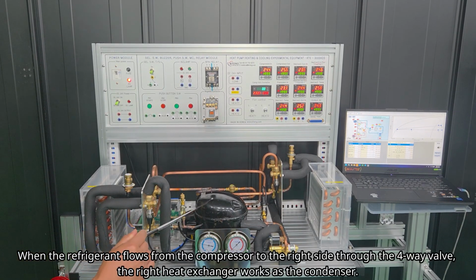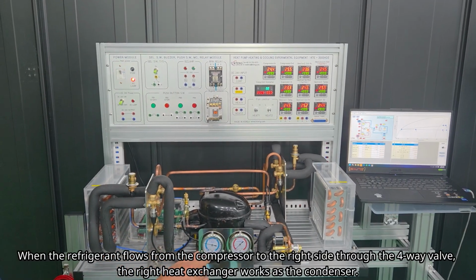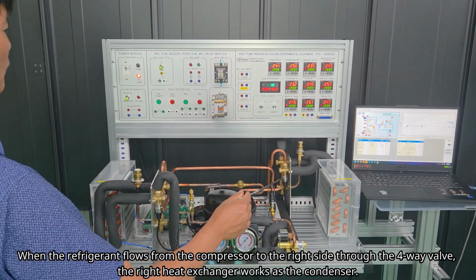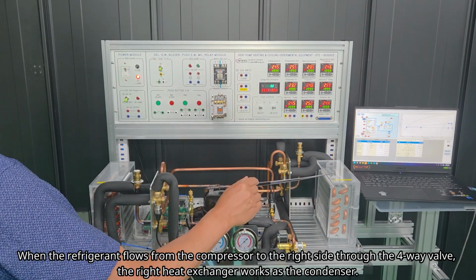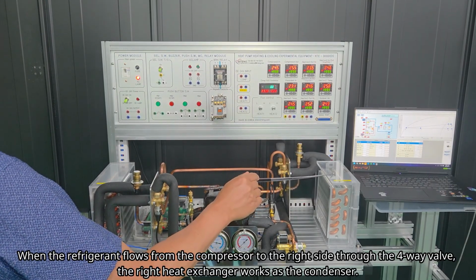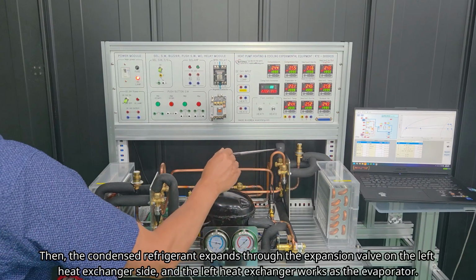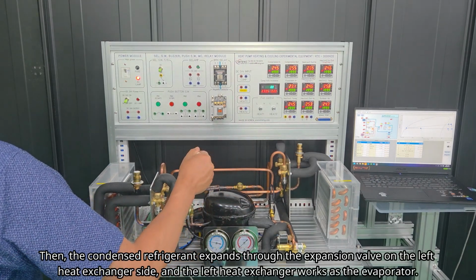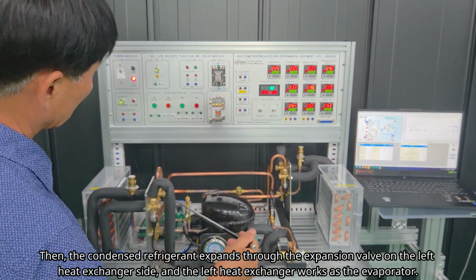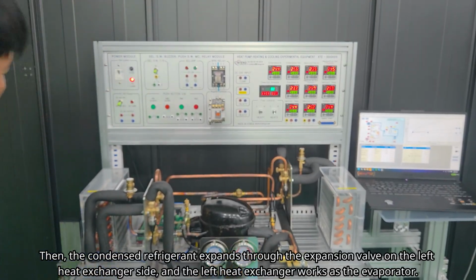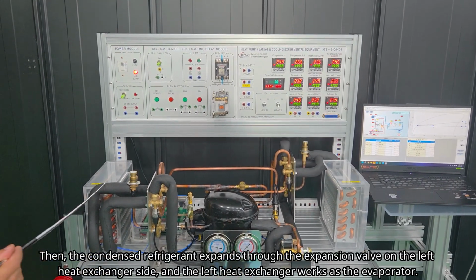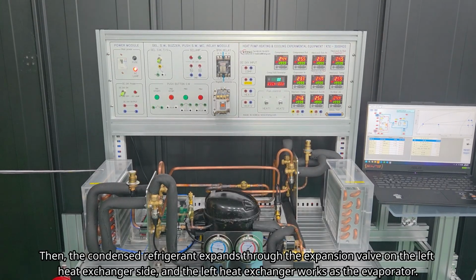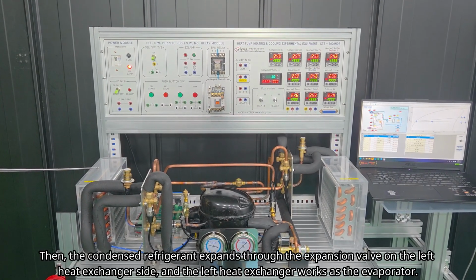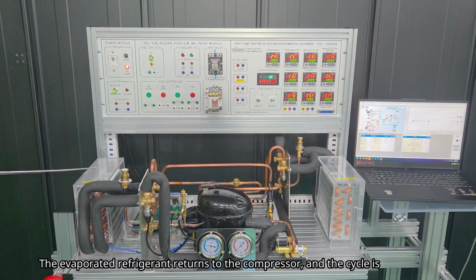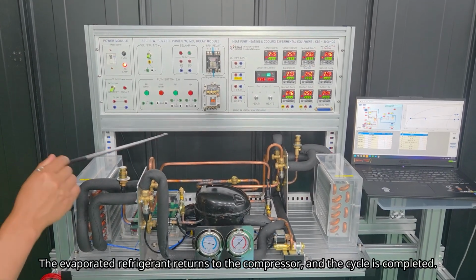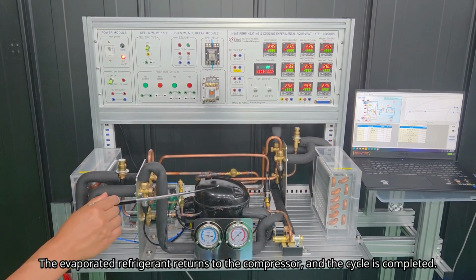When the refrigerant flows from the compressor to the right side through the four-way valve, the right heat exchanger works as a condenser. Then the condensed refrigerant expands through the expansion valve on the left heat exchanger side, and the left heat exchanger works as the evaporator. The evaporated refrigerant returns to the compressor and the cycle is completed.